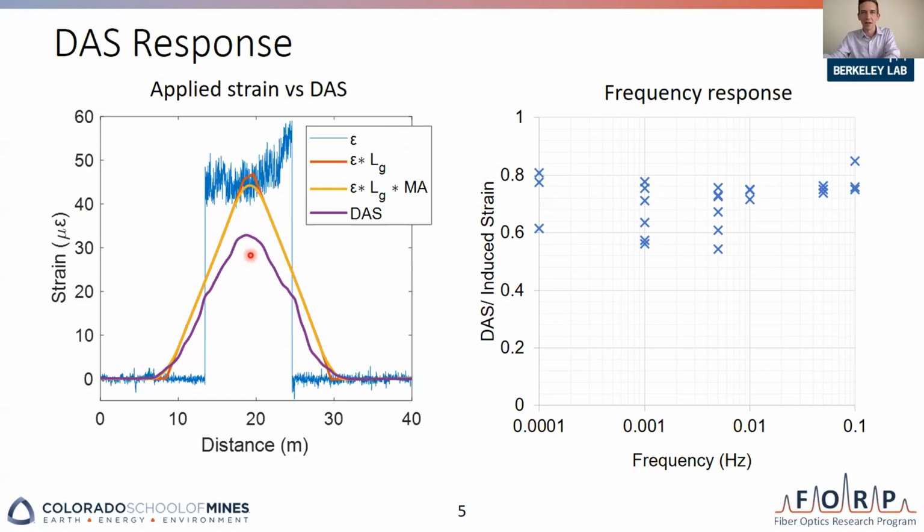Yeah, great. It looks like Eileen has just copied in the document there. Thank you, Eileen. John Dwyer asks, would there be a day-night effect in the desert environment? As I understand, in a desert environment, the changes are pretty rapid. And as we see from Veronica's example, you need to calibrate for temperatures, both the temperature of the box and the temperature of the cable. For the temperature of the cable, it's a bit easier. It will be observed in all channels, so you can apply a subtraction of the general trend for all channels.